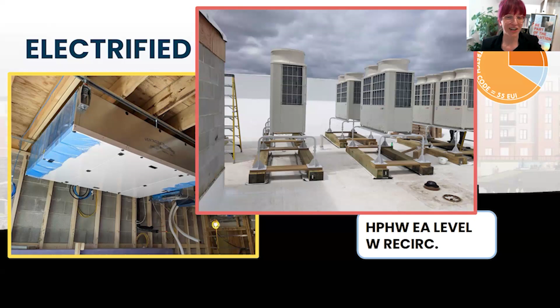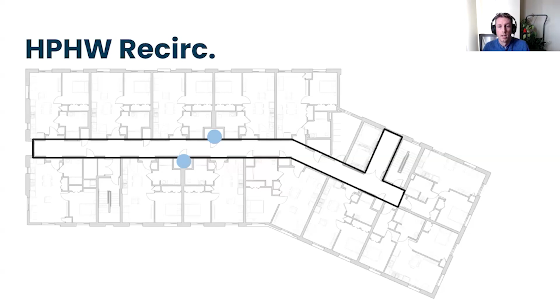Yeah, so in the diagram that Sarah was showing, you may have seen the blue rectangles scattered along a corridor. That was the initial idea. What actually happened in practice was we found that even if we distributed things through the hallways, we weren't quite getting close enough to the point of use to meet the passive house requirement for volume within the plumbing. We see around here that we need to get within about 25 feet because of the plumbing code. We couldn't do that. And so what we did is we got a couple of closets, kitty-corner to each other across the corridor.